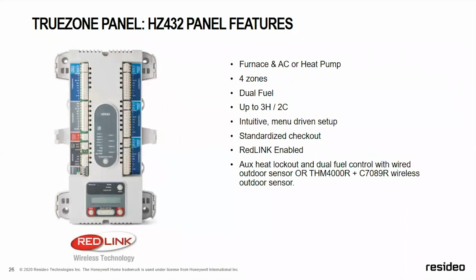This is our Mac Daddy, the HZ432. I love this panel. Furnace, AC, or heat pump, 4 zones. This panel is configured to do dual fuel, 3 heat, 2 cool. Again, intuitive menu-driven setup. You do have to set these up. Standardized checkout. Again, when you're commissioning, you can check your heat, your cool, your fan. It is RedLink enabled. You do again need the THM4000R to do any RedLink.